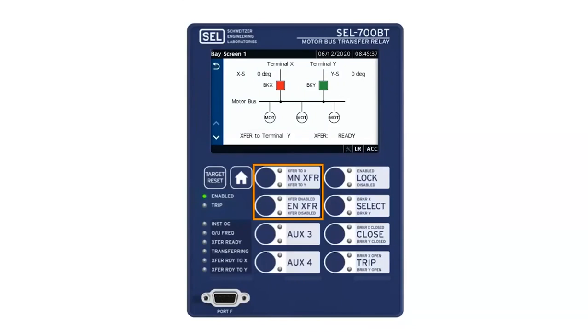Thank you. This is an interesting one. A medium voltage MCC contactor drops out at 50 milliseconds. Can this relay do a fast transfer and in-phase transfer within that 50 milliseconds? Nathan, maybe we can follow up on that question later. We'll note it. Let me just go over that a little bit more.